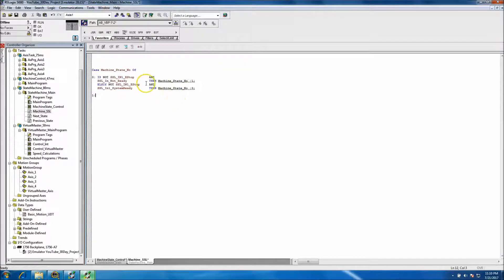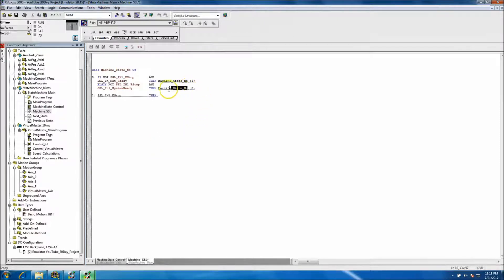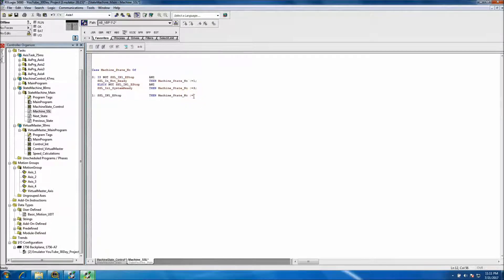For CASE 1: we want to say if an e-stop happens, let's keep this moving — if an e-stop happens then machine state needs to equal zero. So if the machine e-stop happens we want to go back to State 0.